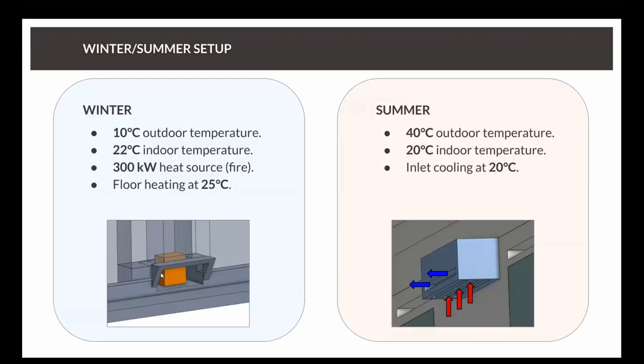We have a couple of different setups. On the left-hand side we have our winter setup, with a fire — represented as an orange block heat source. We have quite a low outdoor temperature — thinking about England, 10 degrees is feasible. Here in Munich it can get to minus 20. The idea is to have around a 20-degree indoor temperature. We also have some underfloor heating, which we can turn on or off. The beauty of simulation is we could turn the fire on or off, run the underfloor heating at different power outputs, and understand how much power we need to get the room to a comfortable level — which helps you design your system.